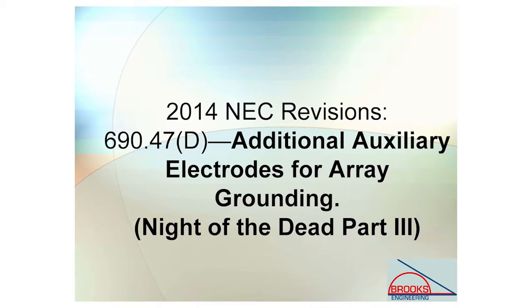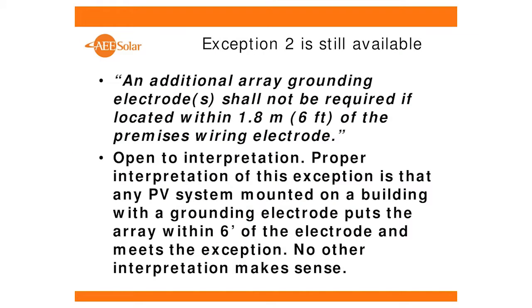And this always goes down better during Halloween, but the auxiliary electrode keeps coming back to life like a zombie, which has frustrated me very much. But it says an exception is still there, and it says an additional array electrode shall not be required if located within 6 feet of the premises wiring electrode. This is definitely open to interpretation, but my interpretation is, since I wrote the original proposal that became this mess, that any PV system mounted on a building that's already got a grounding electrode is already within 6 feet of that electrode. The whole building is considered within 6 feet of the electrode, because it has to be within 6 feet of the building. That meets this requirement, and no additional electrode is necessary.